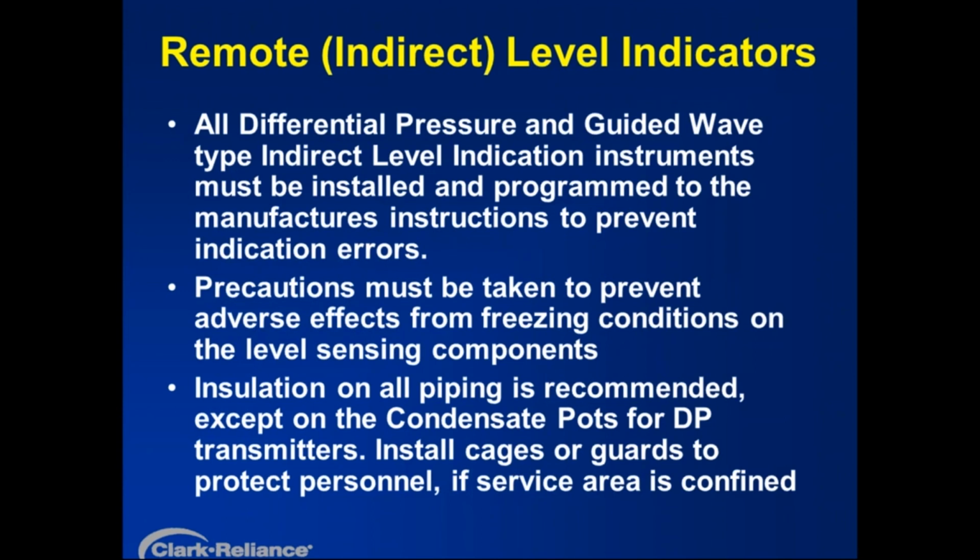Insulation. I'd like to recommend insulation on all the piping leading up to the instruments and up to the gauge glasses. This helps accomplish a couple of things. It provides personnel safety by improving the insulation on that piping, reduces accidental risk for burns by someone brushing up against a hot pipe.